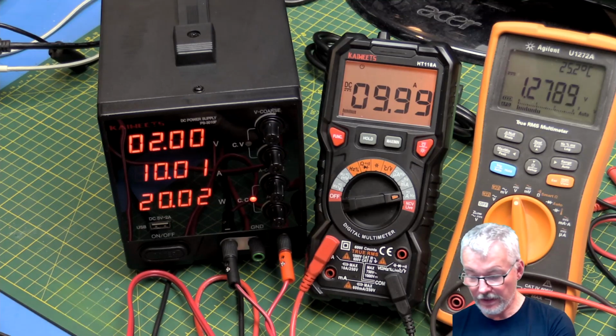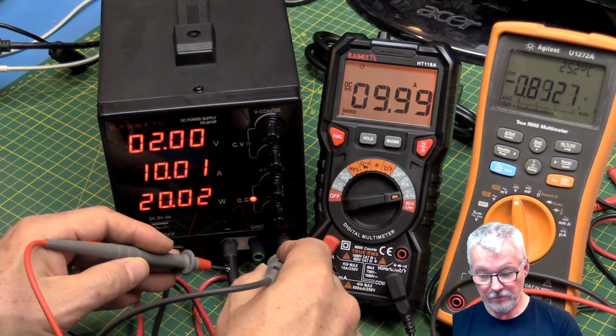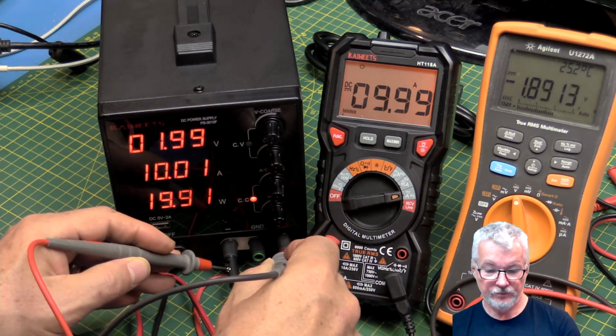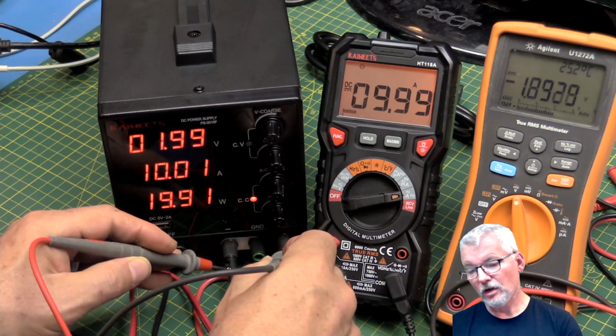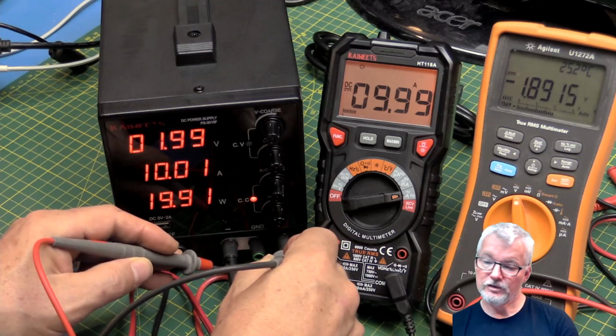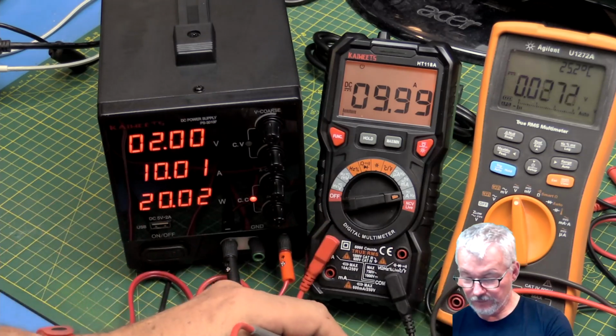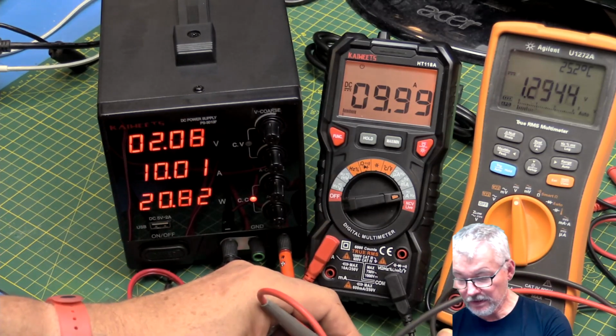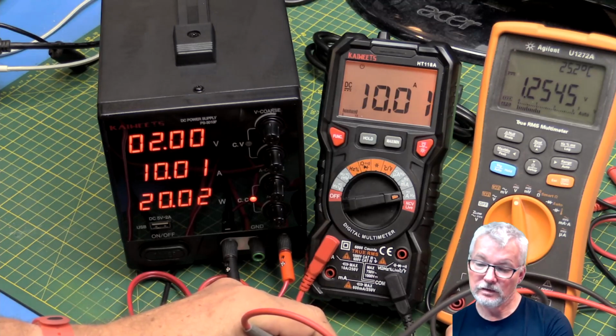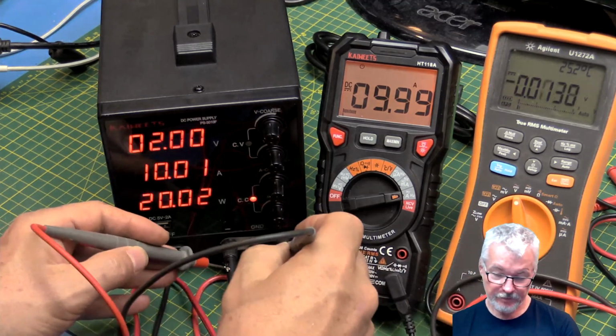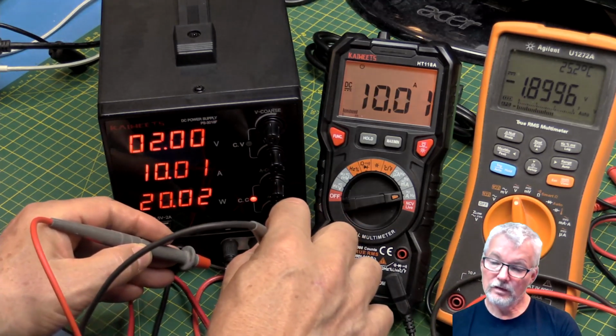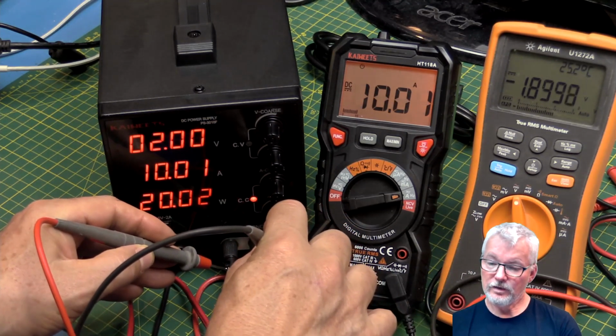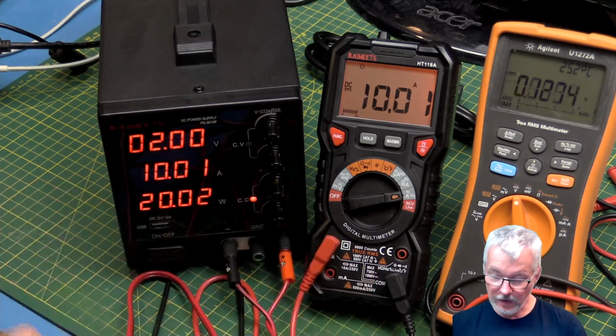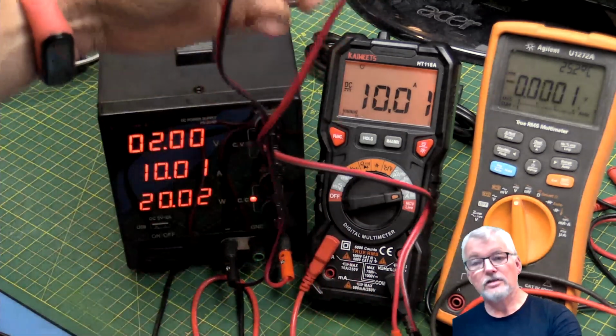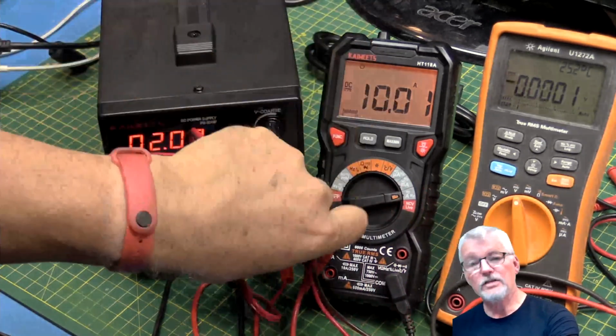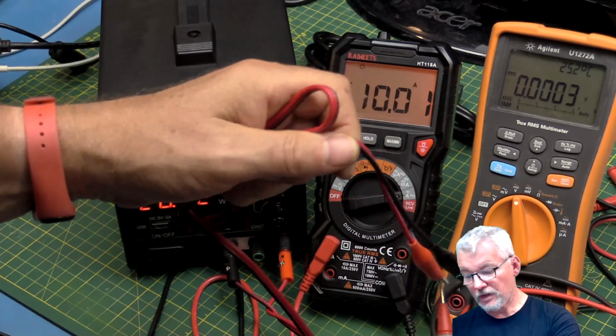We've got 1.2 volts there, and we've got 2 volts here almost. So what that's telling you is it's dropping 600 millivolts at 10 amps. So it's dissipating 6 watts. Yeah, 1.25, 1.89, so say 1.9. So yeah, it's dissipating over 6 watts of power just in this short piece of cable, because it's not thick enough for the maximum current of the power supply.